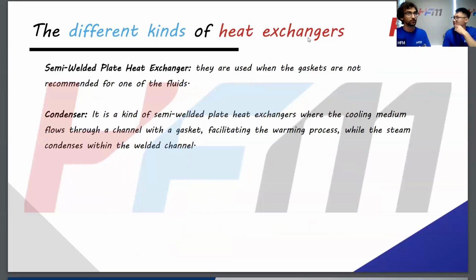One of the most common fluids is ammonia, which is not very suitable for the gasket. That's the reason why we use the semi-welded type when the other fluid is suitable. In this presentation, we're going to talk about a refrigerant fluid where we have to use the semi-welded plate heat exchanger, so pay attention.